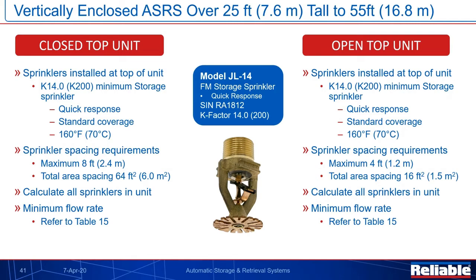Now, the question is, how many sprinklers do you actually need in one of these units? And that's a moving target because the unit itself has different sizes. On the small end, we could see a width of 5 foot. And on a high end, we could see the depth of it be 8 foot. So that's small. We could potentially do a single sprinkler in that unit should we be able to position it just perfectly in the center of the unit. I think a lot of times that's probably not realistic due to the movement of materials inside of there and everything.